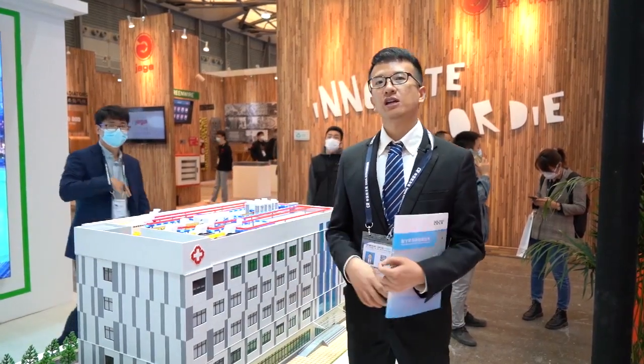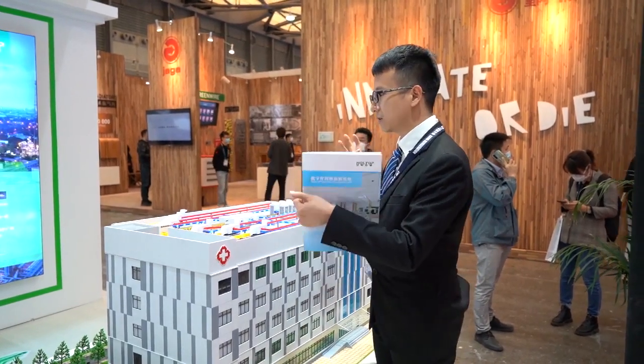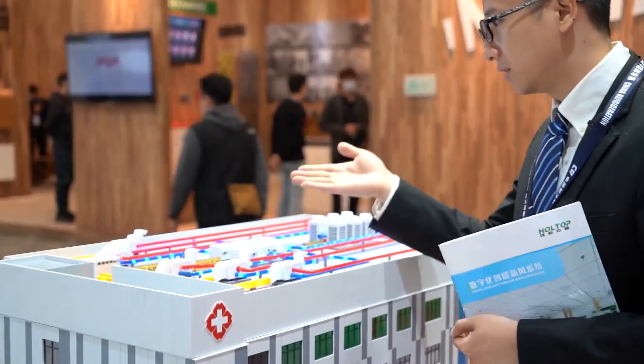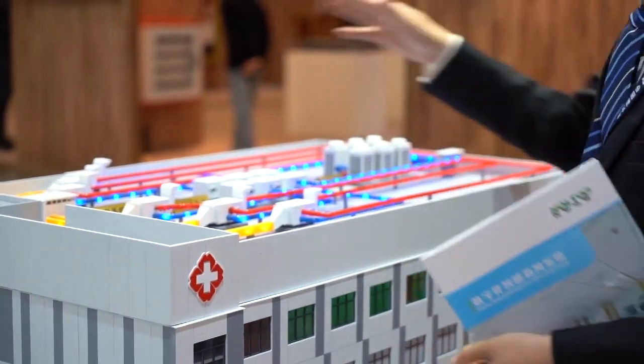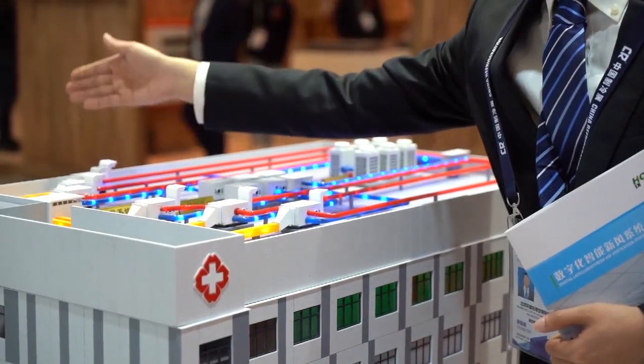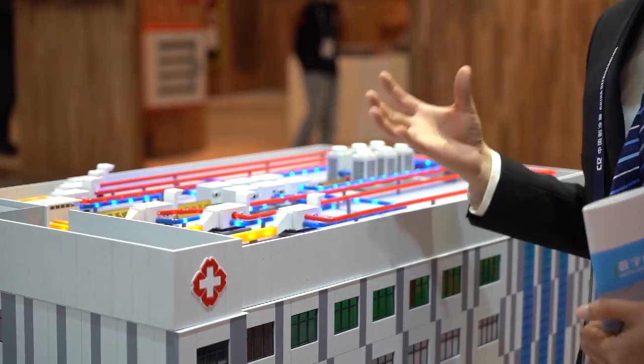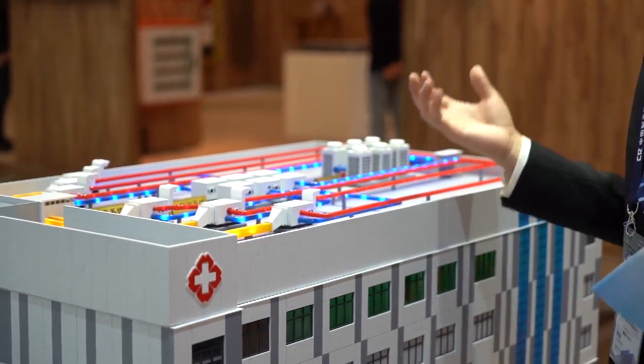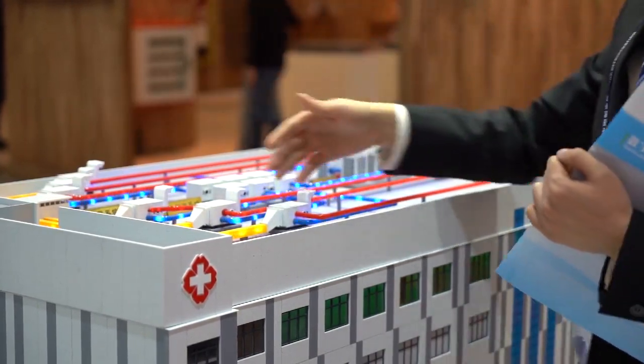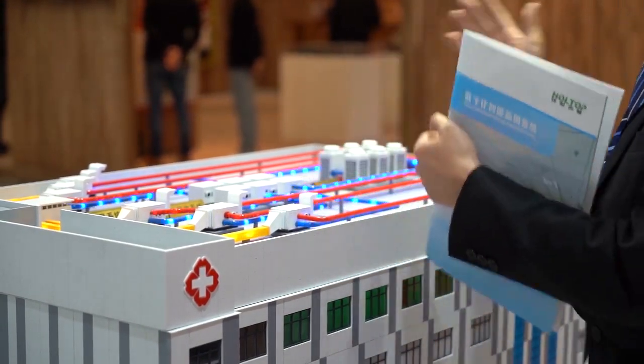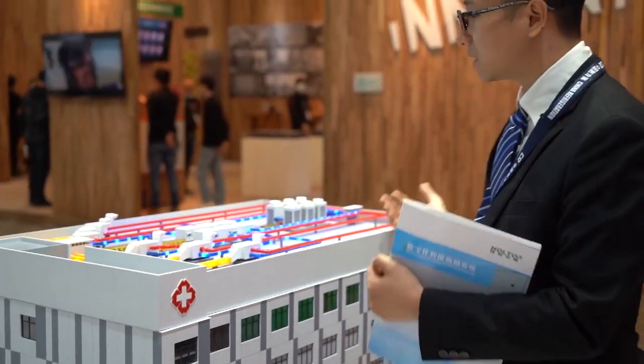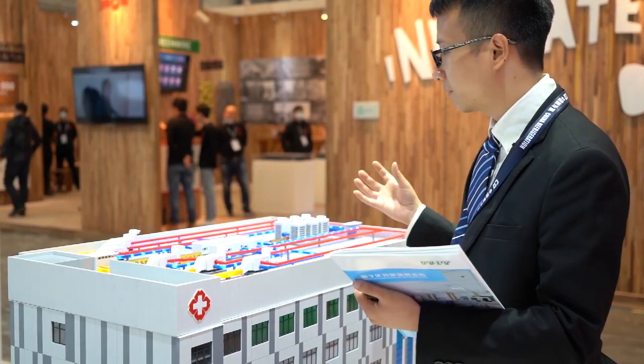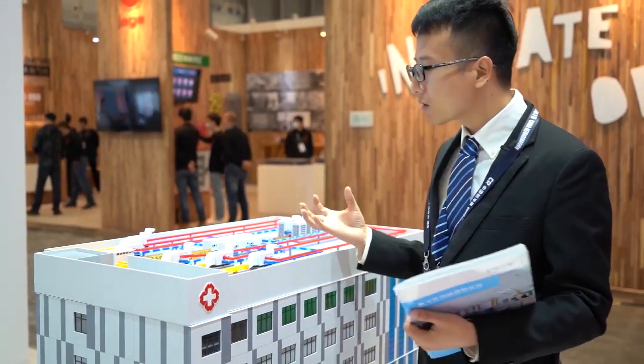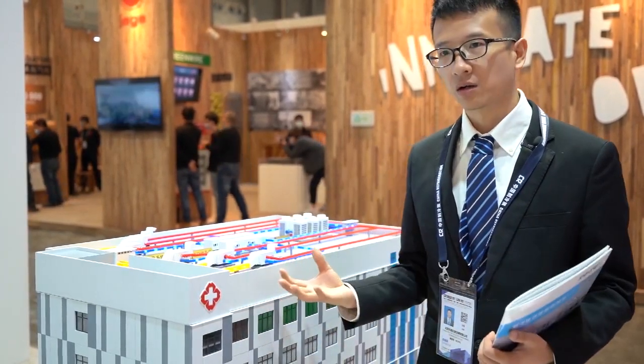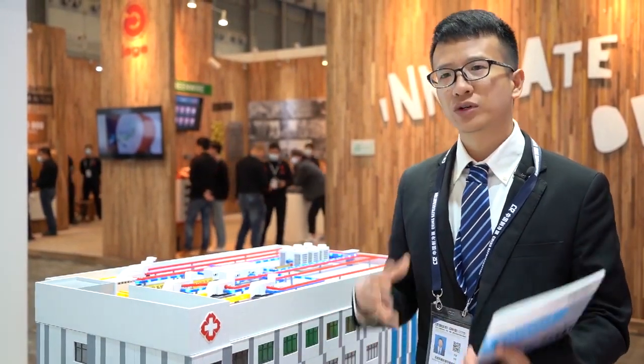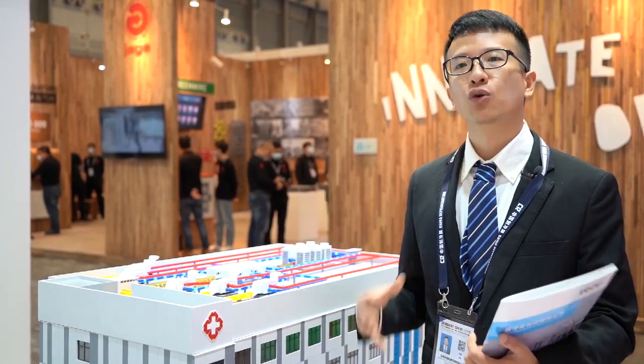In this part, I want to briefly introduce you to the ductings and HVAC design in this system. So please follow me here. In our modular, the first part is the exhausting air system, which is 1, 2, 3, 4, 5, 6. The 6 air handling units are extracting the indoor air from the yellow ductings and exhausting part of the indoor air to outside. And of course, before exhausting the air to outside, the exhausting air handling unit has the energy recovery system to recover energy from the indoor air to mix with the fresh air, which is used to cool down and reduce the energy consumption during the process of cooling the fresh air.